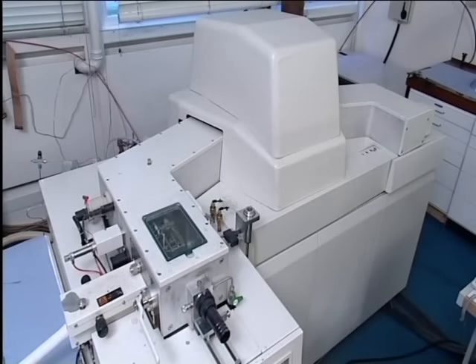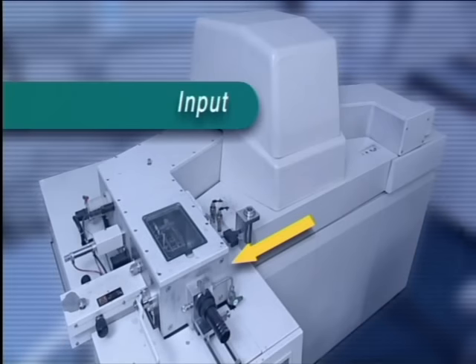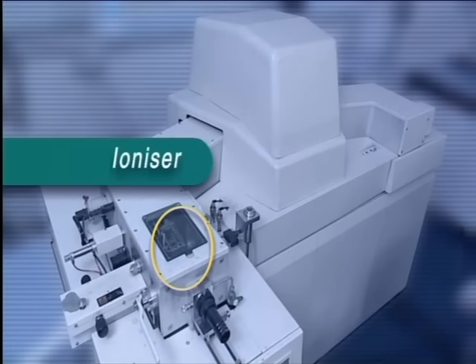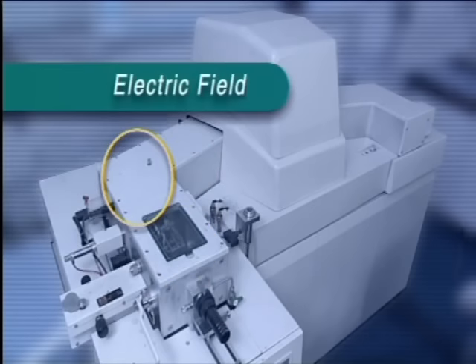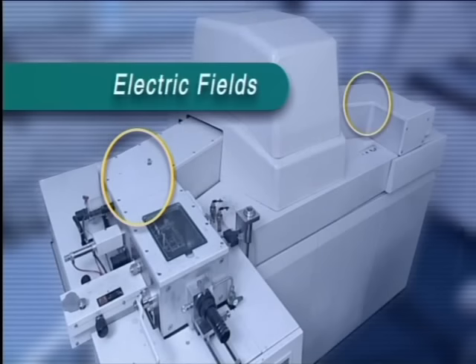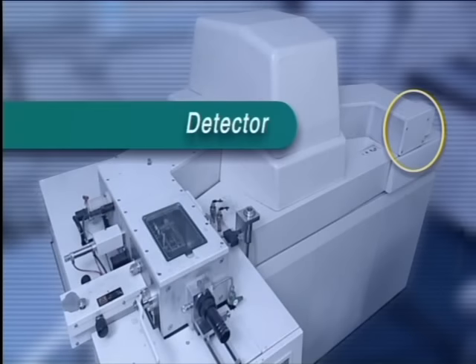This instrument is called a magnetic sector instrument. The sample is introduced here and the positive ions are formed here by bombardment of the sample with a beam of electrons. The ions are then accelerated by an electric field and deflected in a curve by a further electric field. They then bend through a magnetic field and are further deflected by another electric field. The ions then enter a detector. By varying the electric and magnetic fields, ions of different mass can be made to enter the detector.